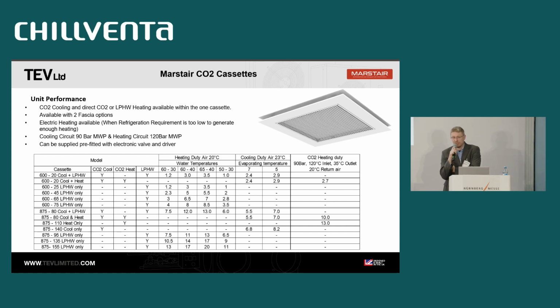And if you try things like false loading, running the system less efficiently, you're just adding quite a lot of cost to the system, and all you're doing is that you still need the same amount of cooling. You're just running the compressor inefficiently to add more energy to the system. From a losses point of view, you probably get better efficiency just by running an electric heater. You get a bit of heat into the space, the fridge starts running, people can't come into the store, and then it becomes self-circulating from that point. So it's just something to give it an initial boost when you first go.